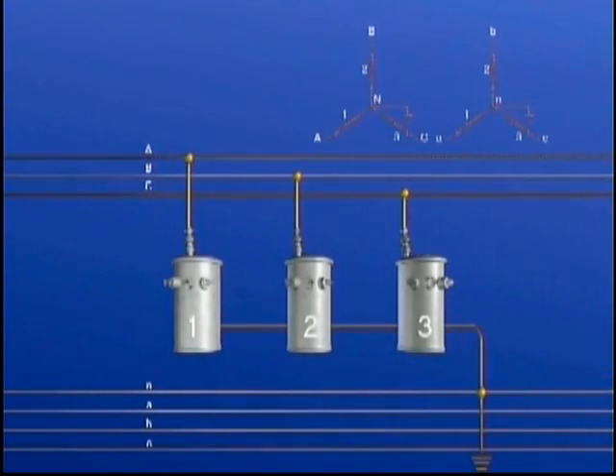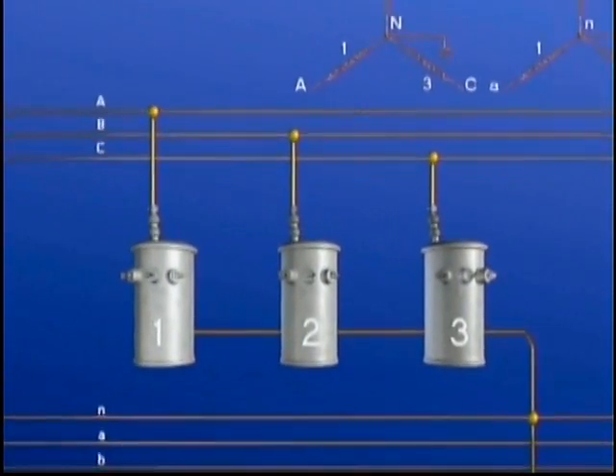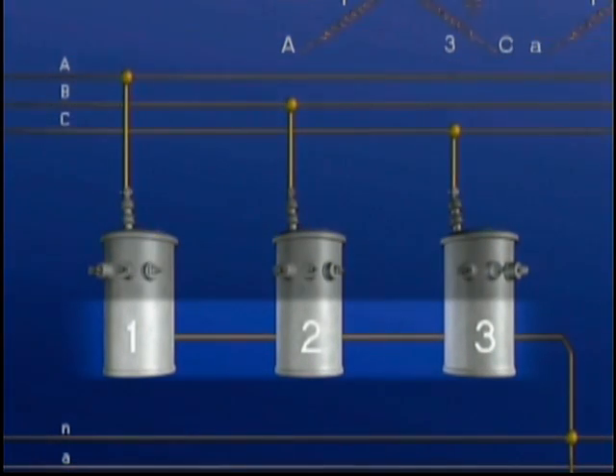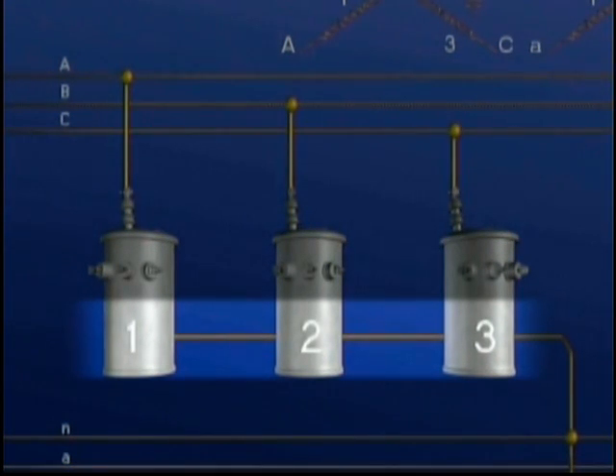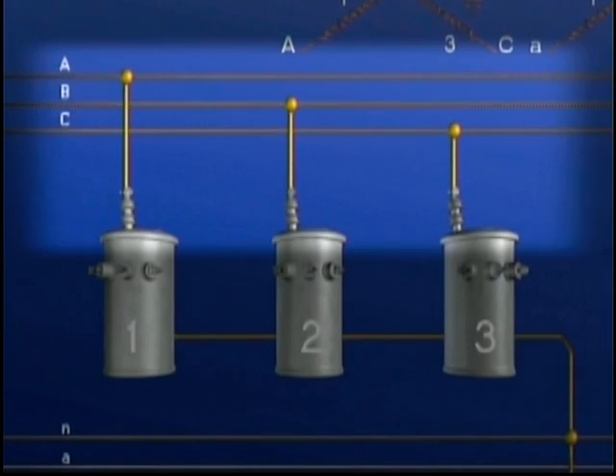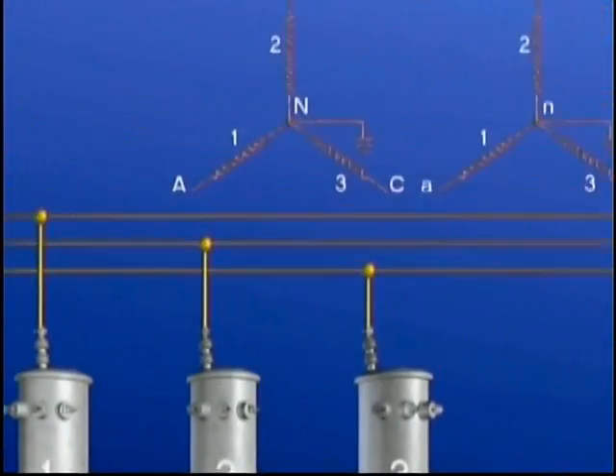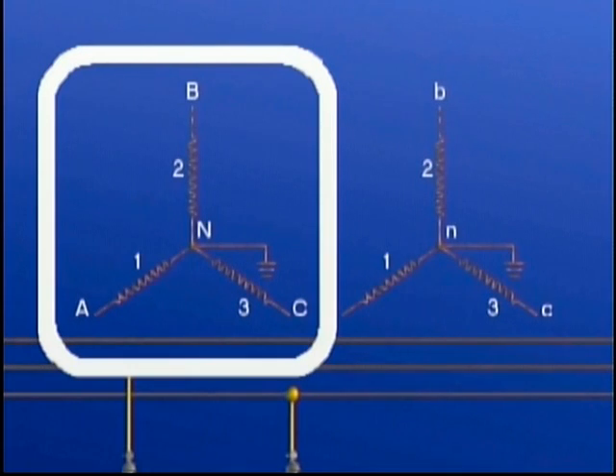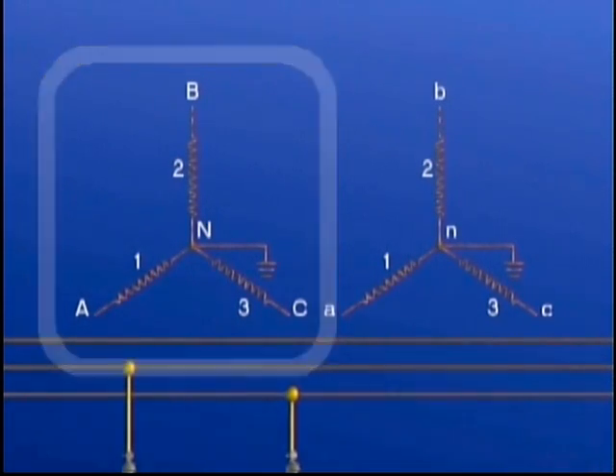Here we have a simplified illustration of 3 single bushing additive polarity transformers. To make our explanation easier to follow, we've labeled the transformers and their windings 1, 2, and 3. The primary windings of each unit have already been connected to the primary distribution system using a Y connection, as we saw earlier. This primary Y phasor diagram represents that connection.